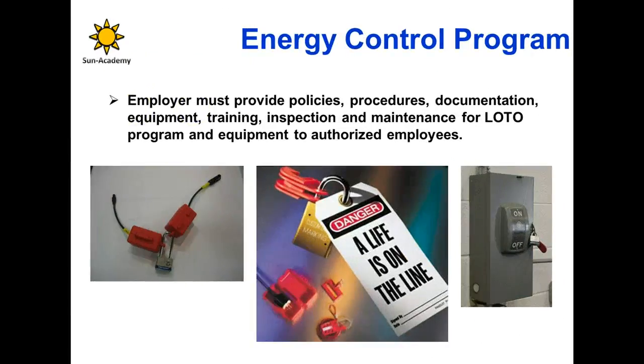Employers must provide policies, procedures, documentation, equipment, training, inspection, and maintenance for LOTO or lockout tagout procedures. Here is a lockout tagout device. Here is a tag, and here is a locked out device on an electrical system.